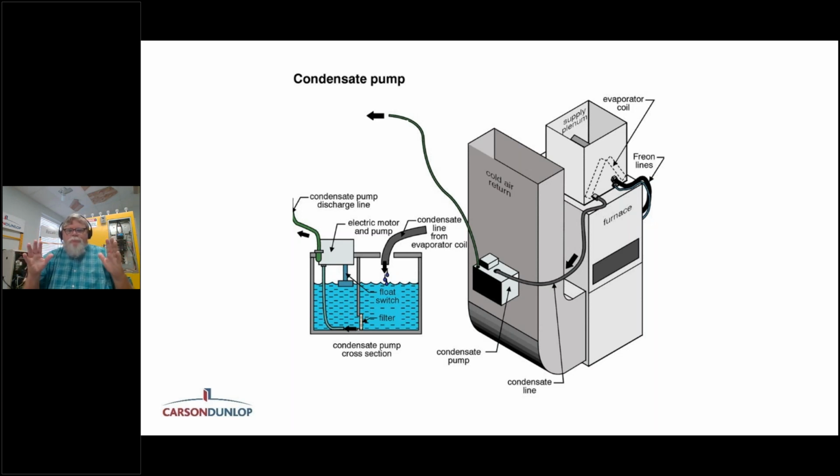But we can also set it up another way, so it will open a circuit and we just cut off the outdoor unit, or using line voltage circuitry, we can cut off the equipment. That way, if the pump fails, we shut the equipment off, people get hot, they call somebody, he comes out and realizes, yeah, the drain stopped up and the float switch shut it down.